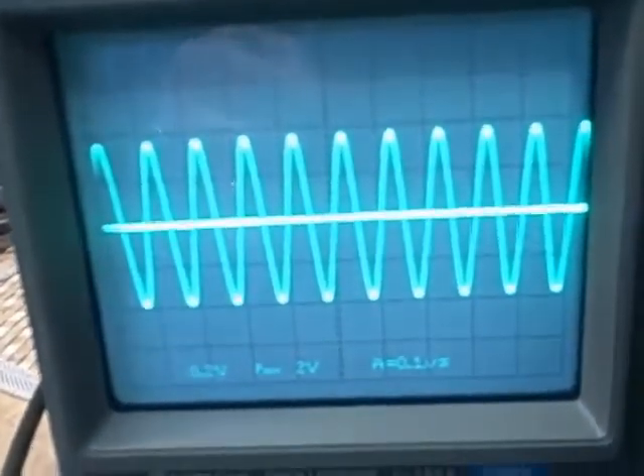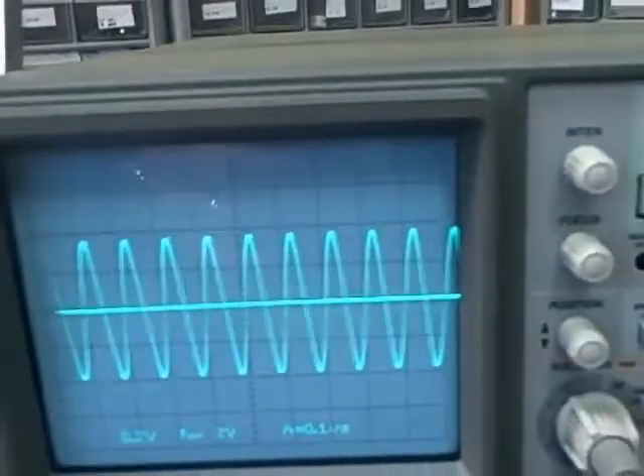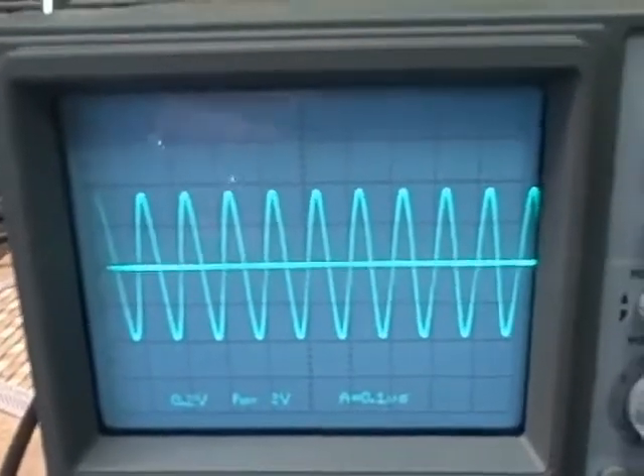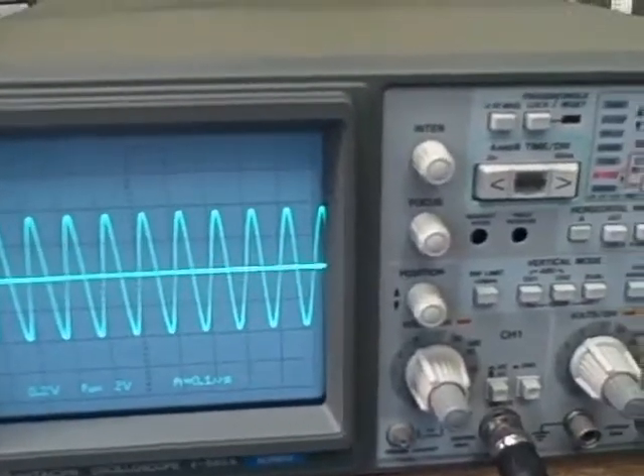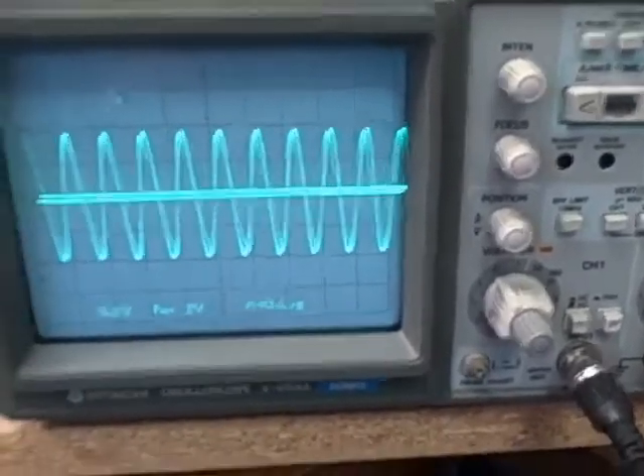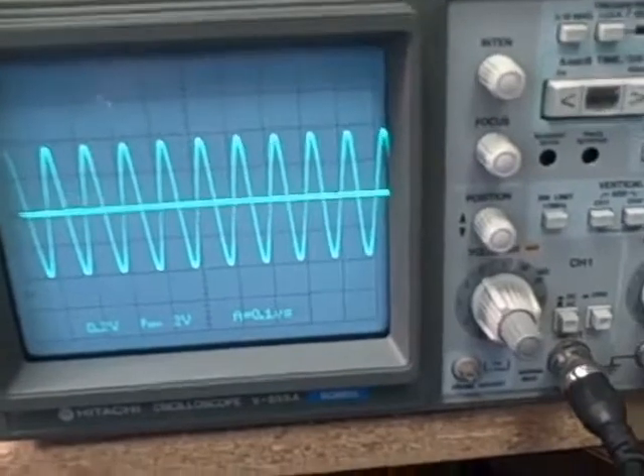It has a good intensity on the display. Plenty of light so no problem. So the basic functions all work well. You can get from 0 to 60 megahertz easily displayed on either channel.